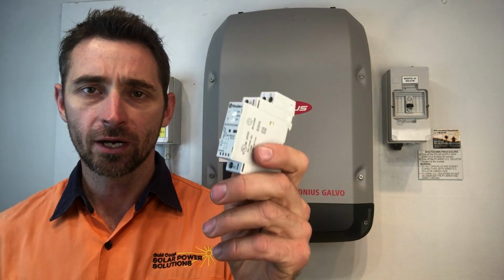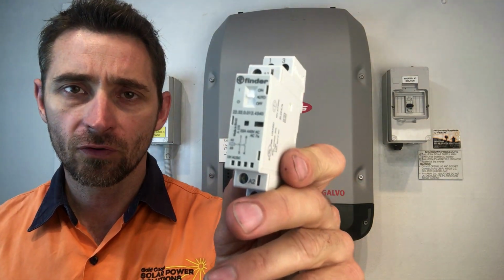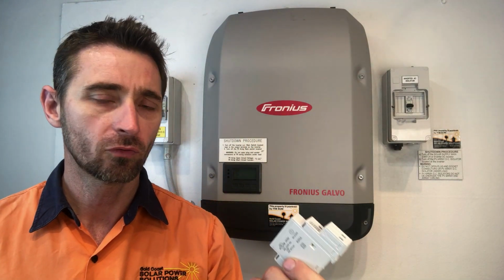The final piece of the puzzle is a contactor with a 12 volt coil to pull in the controlled loads as required. The product we recommend for this is a Finder 25 amp contactor, part number 22.32.0.012.4340. When you have all these parts installed and wired together by a competent solar accredited electrician, we then need to program the inverter to tell it what to do and when to do it.